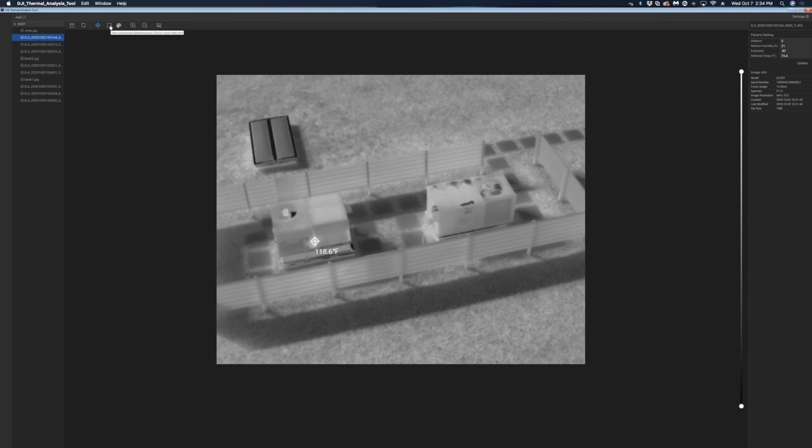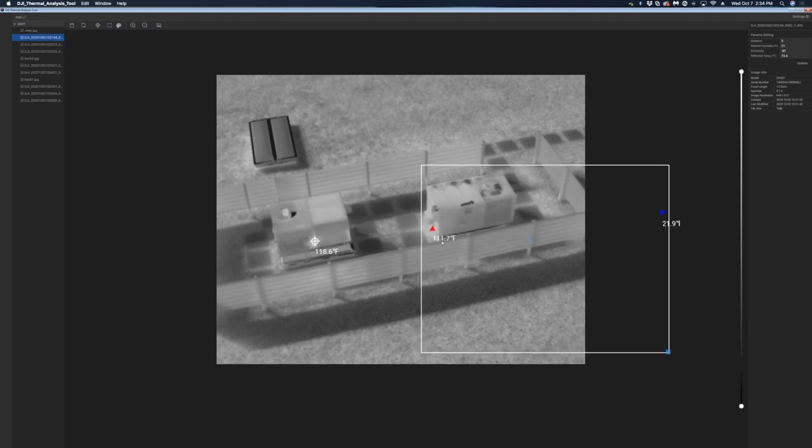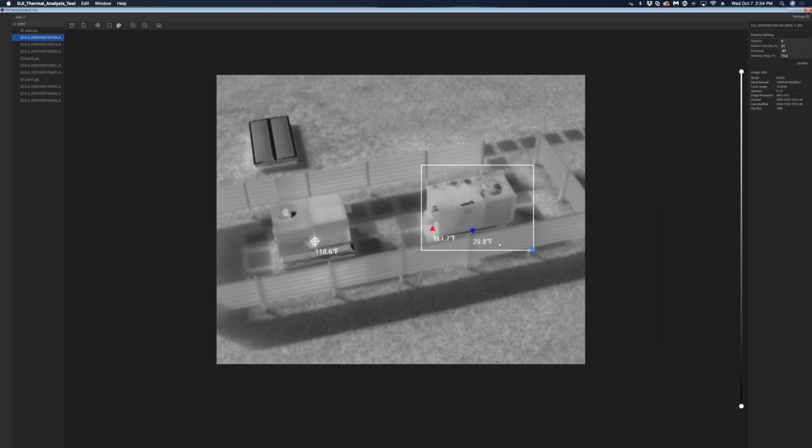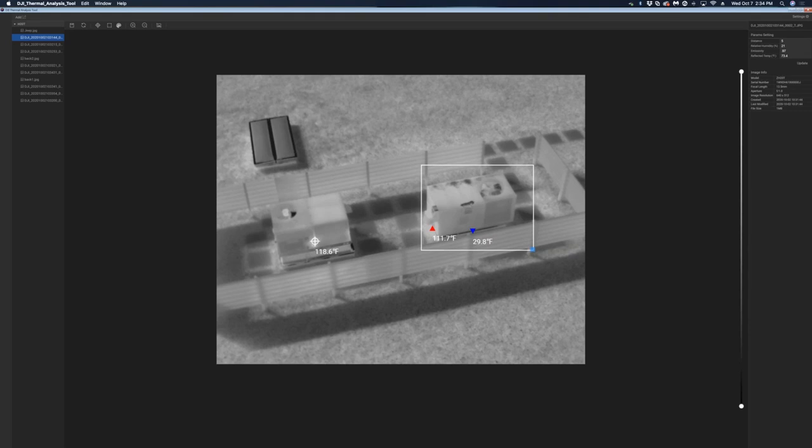Now, if I want more data, more of an area, I can select this marquee tool, and I'm just going to drag it around that whole box. So now I can see that my lowest point... Let me drag this back in here. I think this is one of these issues of using VMware. My mouse control is not the best on this app. So right there, it shows a spot where the lowest temperature is, which is 29.8 degrees, and the hottest temperature being 111.7 degrees. This is how you would kind of build a report for somebody. If I'm going to take and provide this to the HVAC company, I'm going to have these spots on here, I'm going to have these different measurements, and then I'm going to save this so that they can then analyze that and determine, hey, that's probably something we should go out and check because it shouldn't be running that hot.